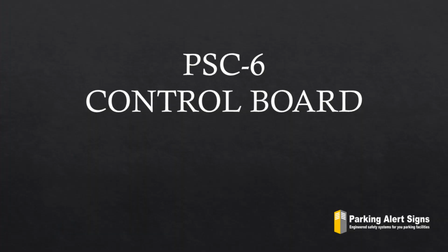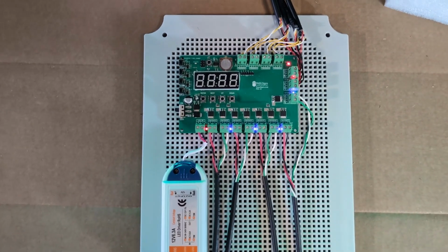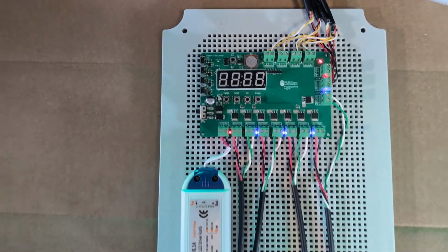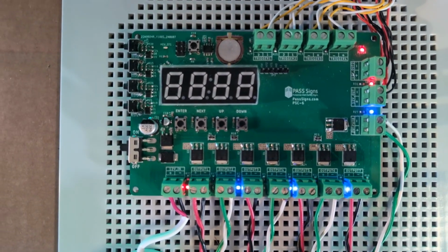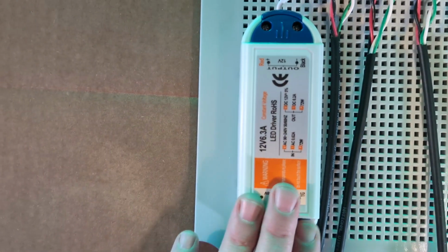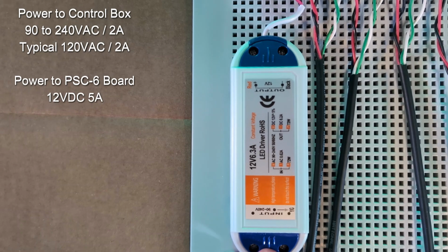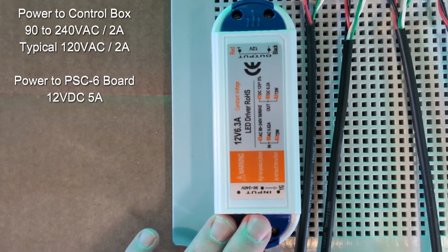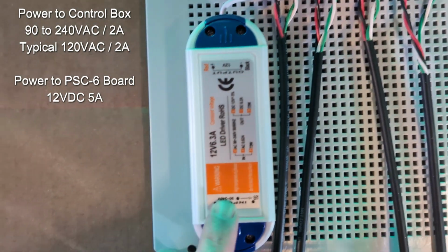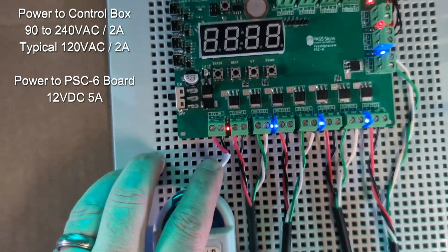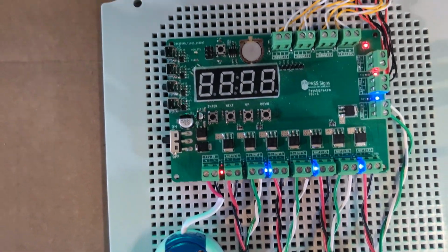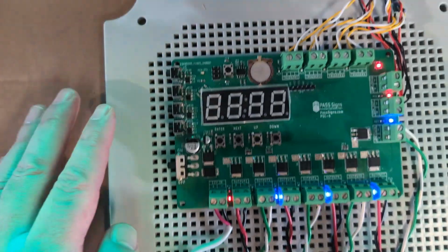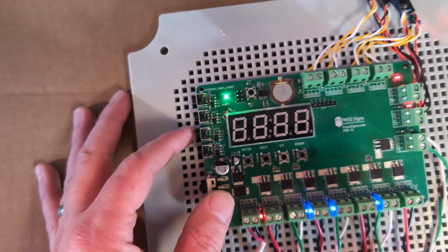Okay, let's take a closer look at components. Now, I'm freehanding the camera here so you guys can get up close and personal to the control board. So the first thing that we have is our power supply. It's bringing in AC voltage, typically 120 volts, but it can go all the way up to 240 volts. And it's transforming that down to 12 volts DC. We have a power switch here, and we have our 4 test buttons.